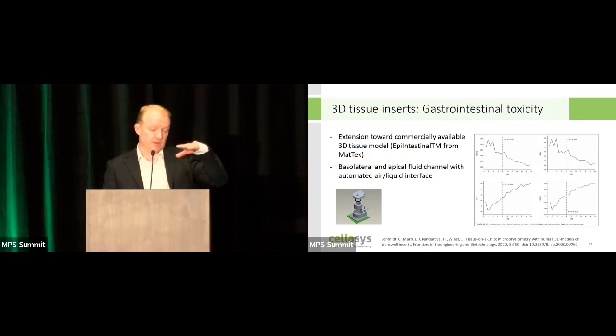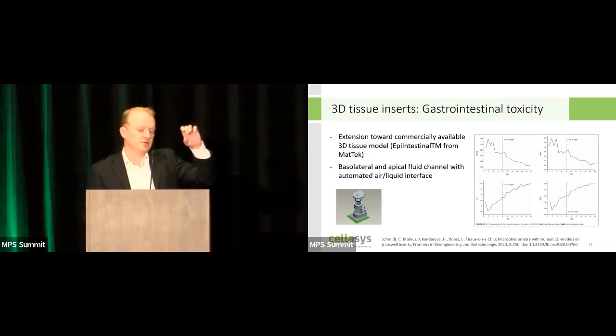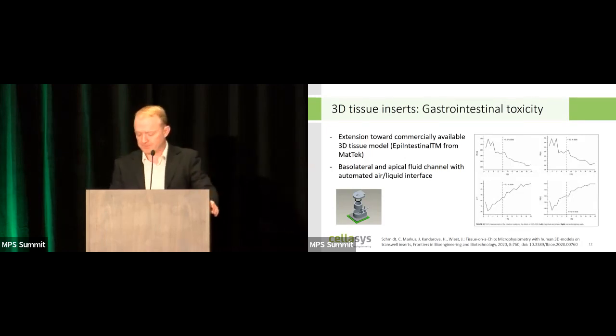So we can exchange the media below the tissue insert. Then we can add media on the apical side, but we also can remove it and leave it to the air-liquid interface. And only if we add media on top again, we can, for example, make a TEER measurement across the barrier of that function. And I have to say, that's all in the incubator, and everything is automated. So nobody has to open the incubator to exchange some fluidics or to insert some chopsticks. So the fluidic system is automated, and the measurement system is automated.